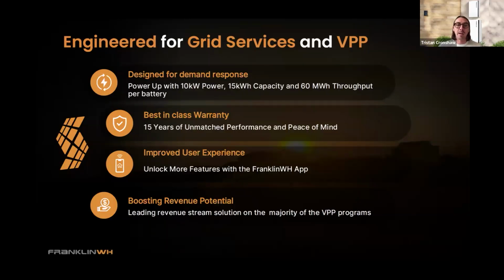Yeah, that's correct. We recommend somewhere between a 50 and 70% run duty, as we call it, to minimize any harmonic distortion. The issue is if you have the generator throttling, it can still pass through the Franklin system to loads. And our batteries are very sensitive to THD and any type of power coming in. So it's very easy for us to not charge if you were to exceed an appropriate harmonic distortion, but you run the risk of potentially damaging appliances.